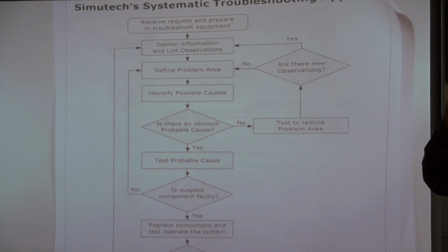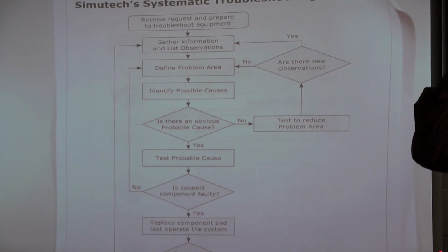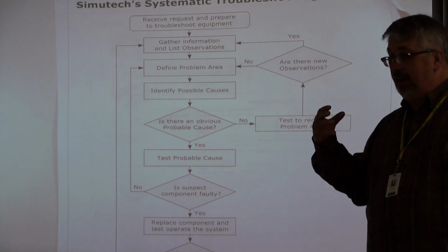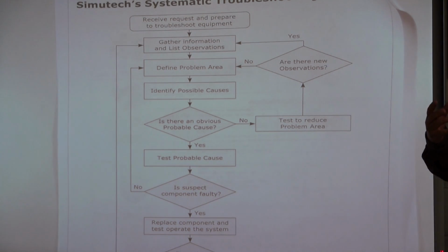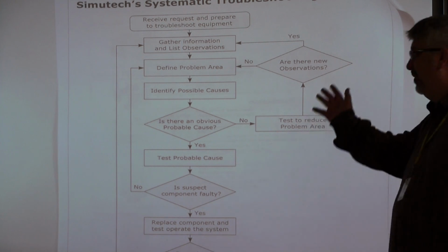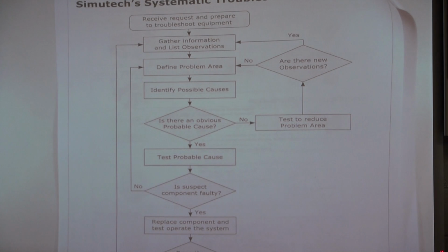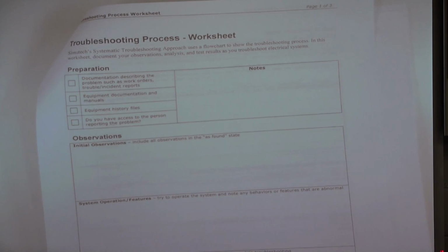And if you're not careful, you'll make some broad assumptions, just like I did a moment ago when we were troubleshooting. So don't just apply the shotgun method of troubleshooting. The shotgun method just basically says, I'm going to change something out until something fixes it. This next page is for the observations you made, what you noted is working, what isn't.